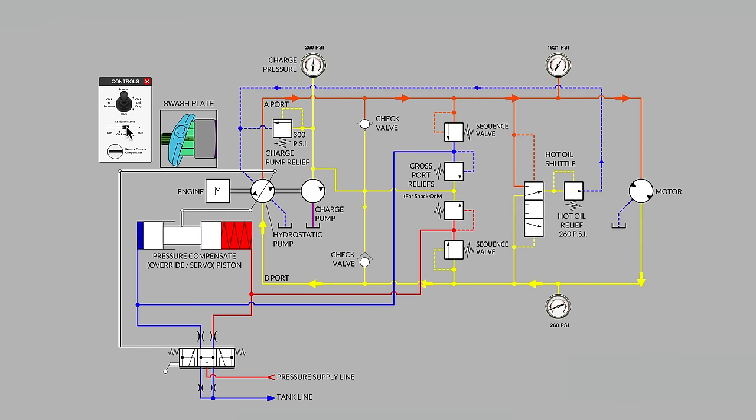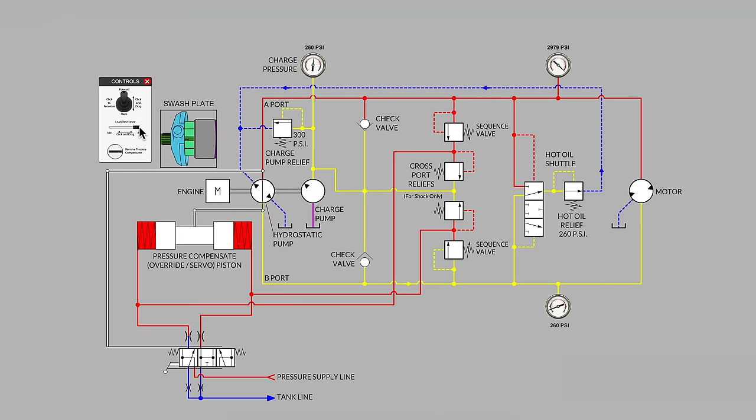But when overloaded, when the hydraulic motor way down there on the right hand side is overloaded, as you're about to see the sequence valve pop, but maybe this time keep your eye on that control piston over by the pump on the left hand side and see what happens. There we go. It returns the swash plate to the neutral position.